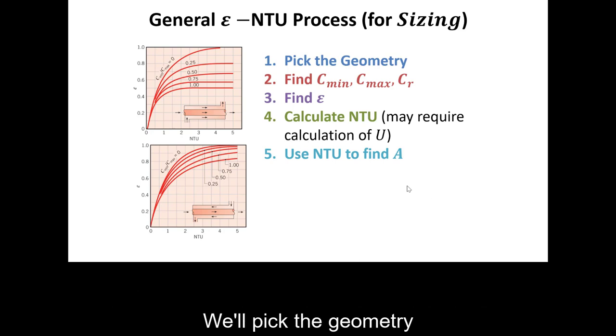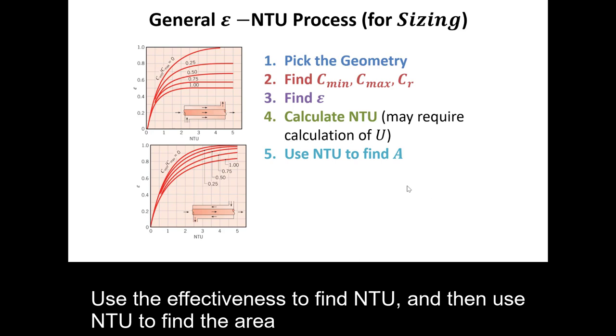The process for effectiveness NTU for heat exchangers when I'm looking for the sizing is the following. We'll pick the geometry. Find the fluid heat capacities and the ratio. Get the effectiveness. Use the effectiveness to find NTU. And then use NTU to find the area.